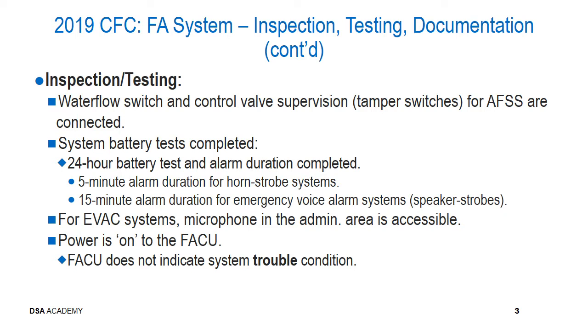Need to ensure that the system battery tests are completed. This would be the 24-hour battery test with the inclusion of the alarm duration. Remember, that's 5 minutes for horn strobe type systems and 15-minute alarm duration for emergency voice systems utilizing speaker strobes. For emergency voice alarm systems, EVAC, ensure that the microphone is in the admin area and is accessible to staff.